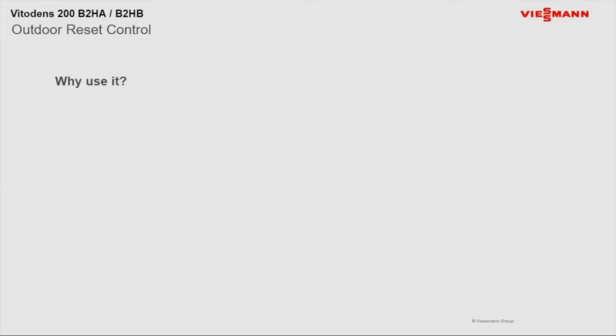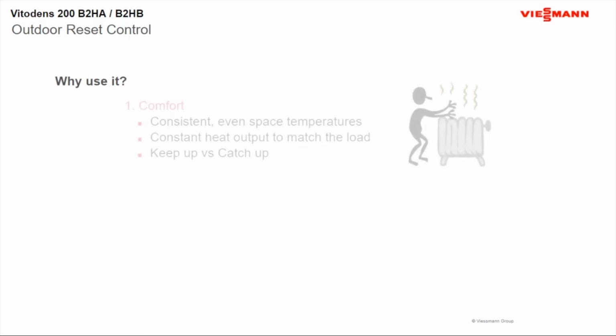So you're not going to have that nice arching curve that you normally want to see to get these boilers condensing. Because we want our return water temperature coming back to any condensing boiler below 140, right? So we need to be creative in how to strip all that heat out before it reaches the boiler, so our return temperatures are down below 140. So we're condensing. That's how we make these boilers go up to 95, 97% efficiency. So outdoor reset, why do we want to use it?